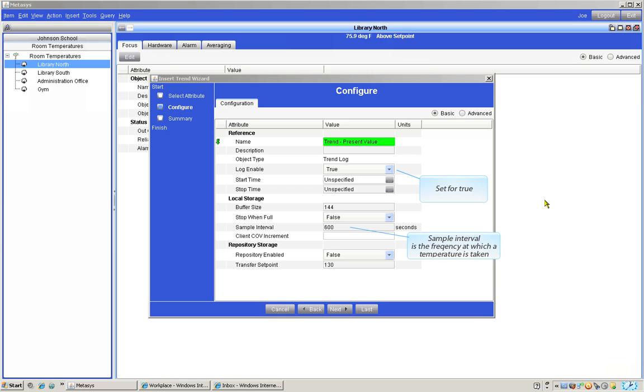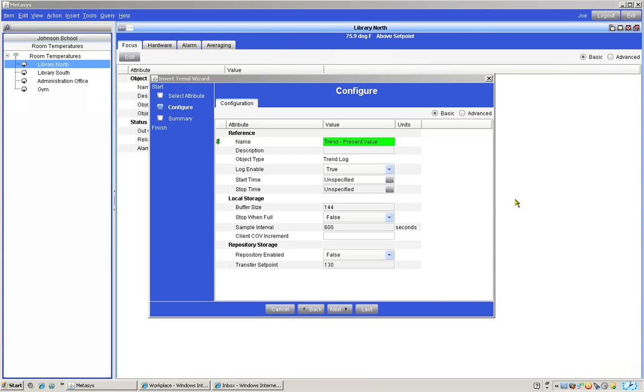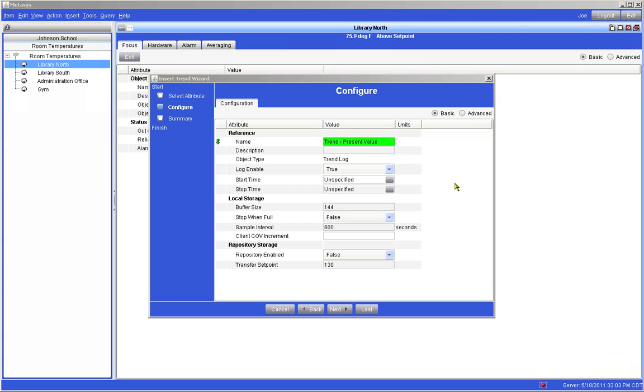However, notice the sample interval area. This is where we will tell the trend how often to obtain a sample temperature. In our case the sample rate is to take a temperature sample once every 600 seconds or every 10 minutes. You can change that if you like. I will stay with the 10 minute sample rate.